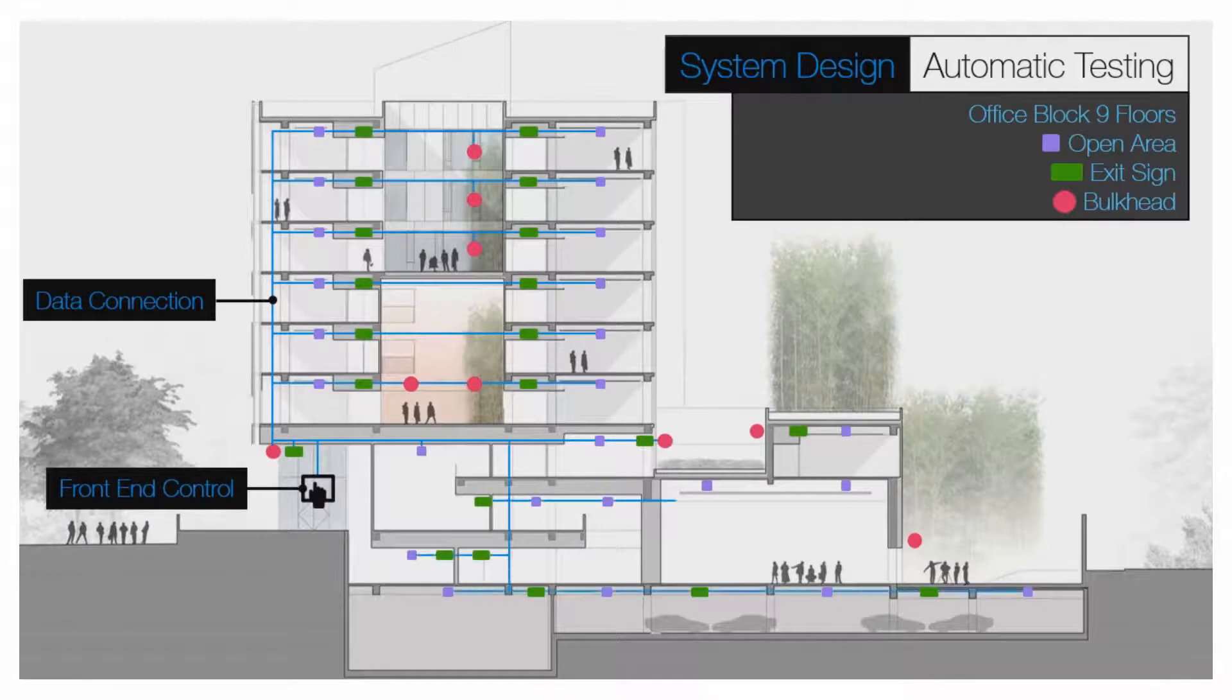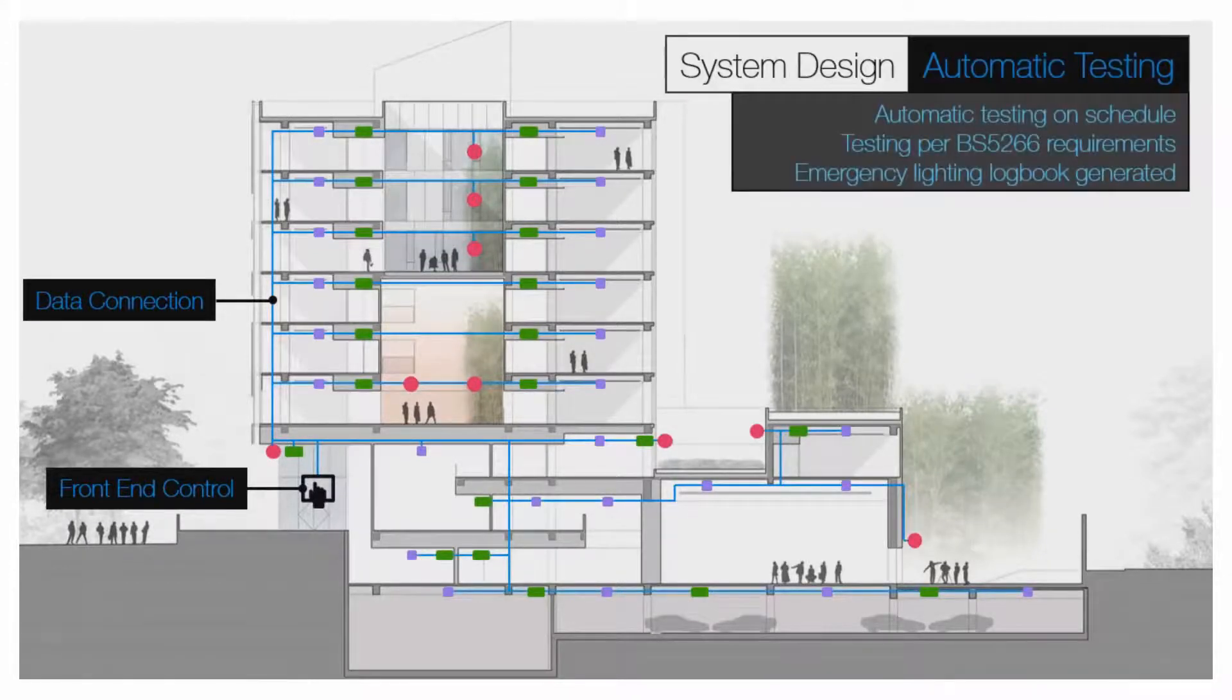Let's have a look at this emergency lighting system. With automatic testing, the luminaires are addressable and respond to instructions from a front-end control. A data connection to the luminaires allows the system to communicate and carry out the testing automatically. Complete records of test data are retained in a format that complies with the BS 5266 testing requirements. This can be presented to the fire authorities for inspection.